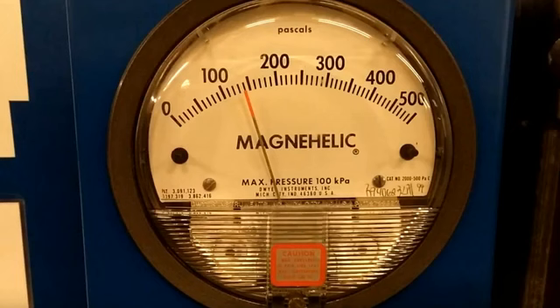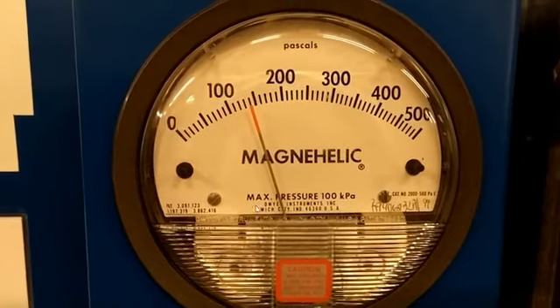Now, as the filters pick up that dirt, they do create a lot of pressure resistance, which the fan has to overcome, and that's obviously very energy intensive. I'll just show you a clip here. So here we've got the dial, which is reading in pascals the amount of pressure difference across there. So we've got the high side pressure there and the low side pressure there. And the high side reads the face of the bag filters there, so the air is passing across and into these filters, and then it's coming out on the other side through the filter bags there.